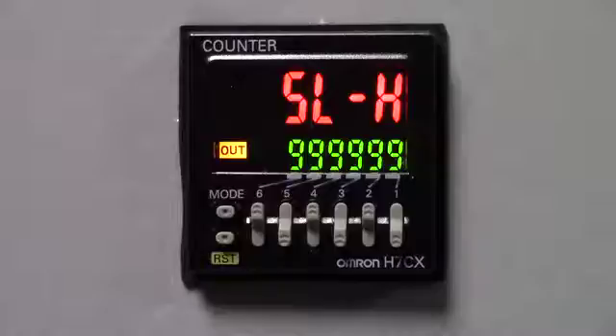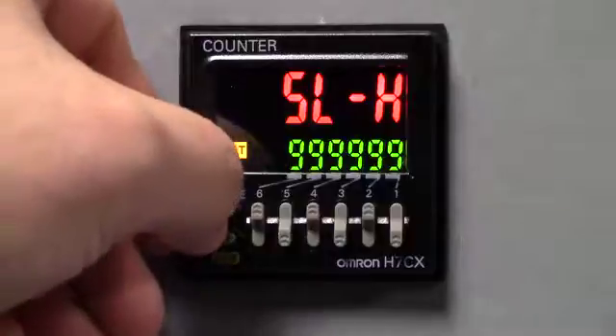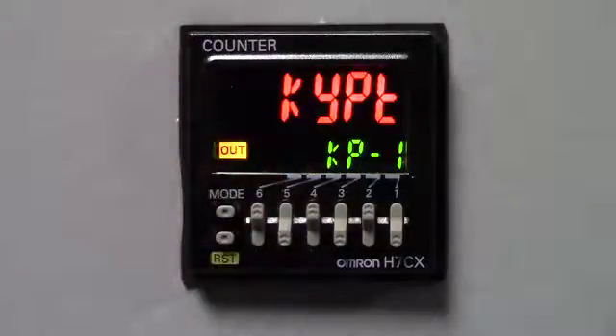So what we could do here is, for example, if our set point was 25 or 50 or let's say 100 or 500, we could set the SL-H equal to that number. So then we will not get any false numbering or false counts from the application. It would stop at that number. So we are going to keep it at the factory default and continue on to the key protect menu.